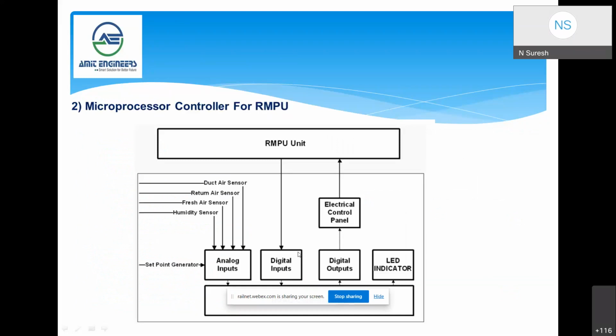This is the schematic of the RMPU and the microprocessor controller. There is an electrical control panel which is provided inside the switchboard cabinet, and inside the switchboard cabinet itself, the microprocessor controller is fixed, which has analog inputs, digital inputs, digital outputs, and LED indicators.